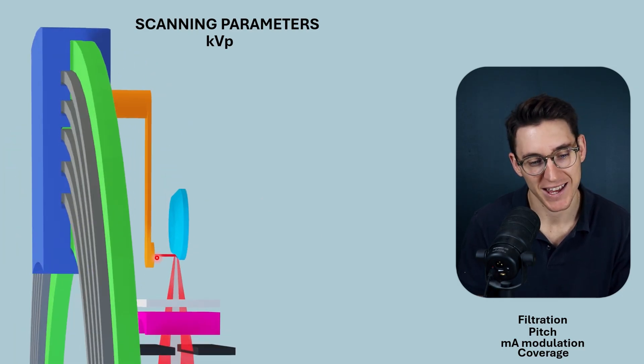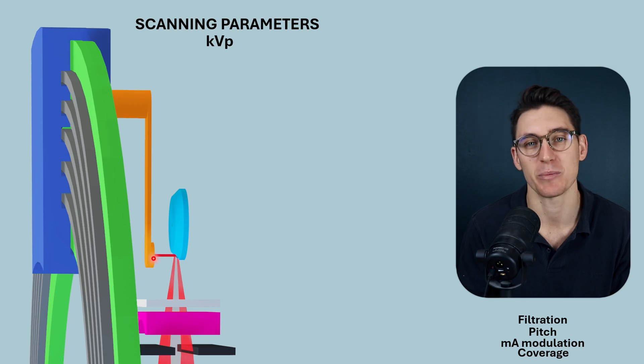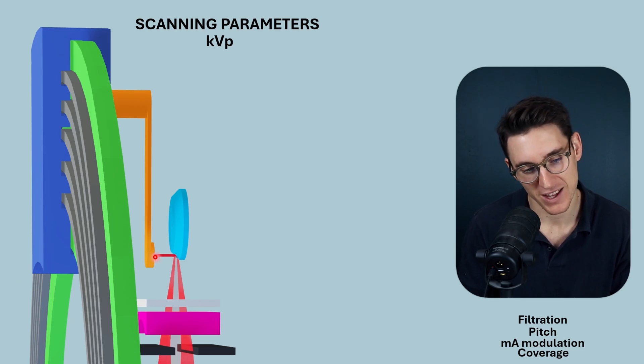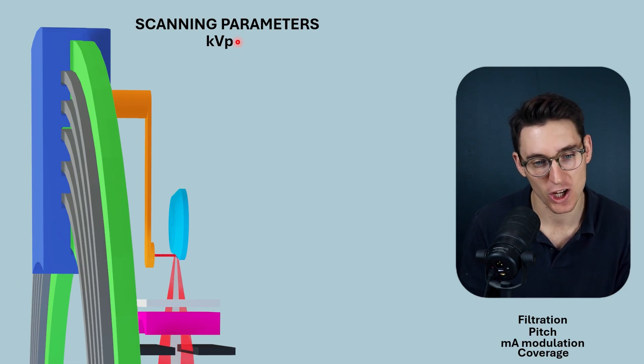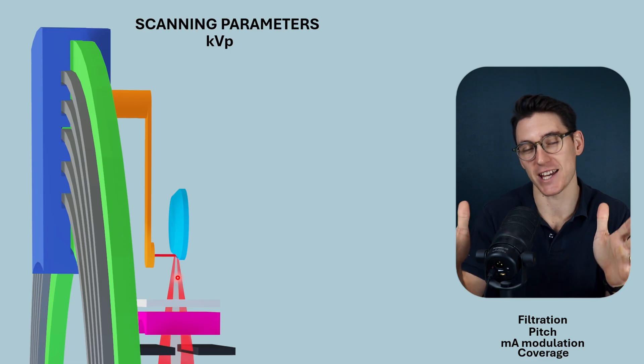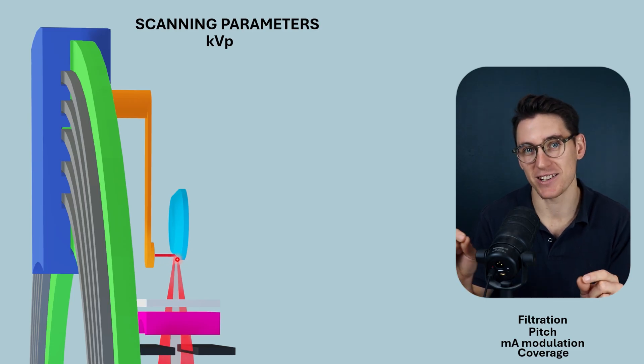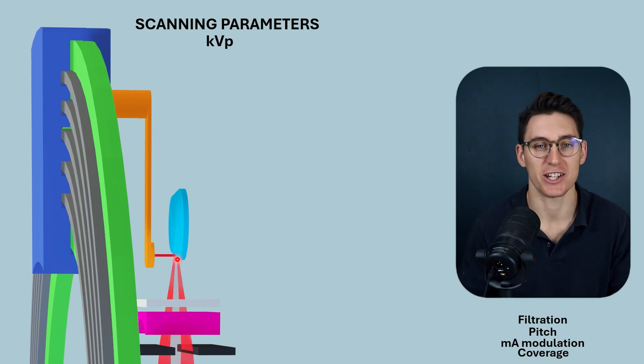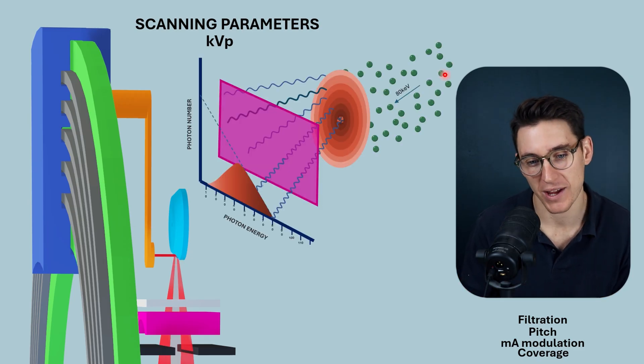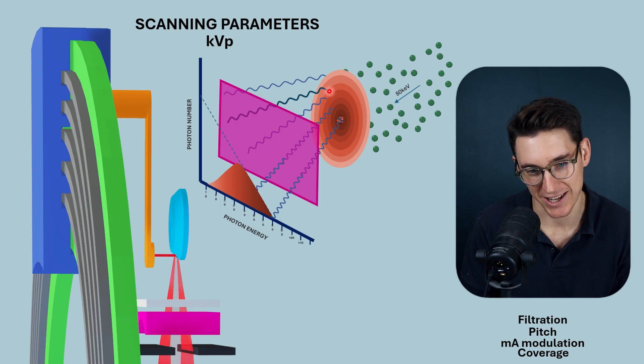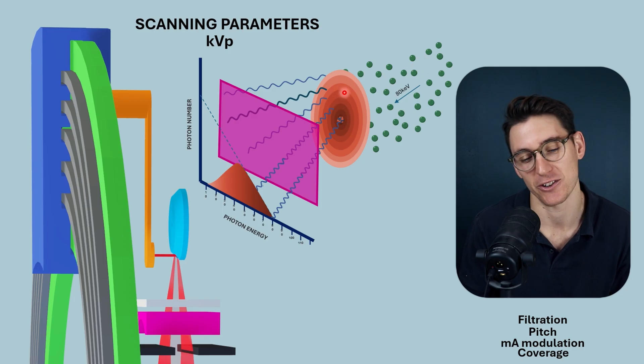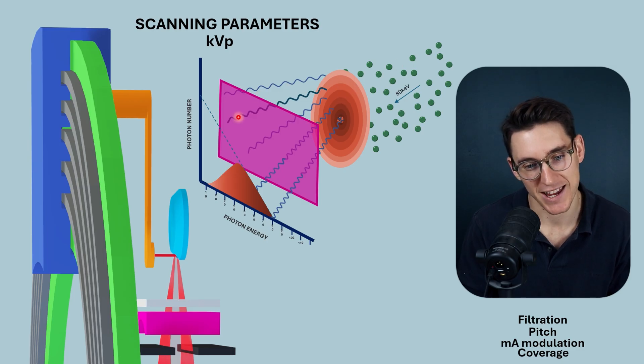Specifically, we produce x-rays by accelerating electrons from the tungsten filament in the cathode towards the anode. The number of electrons and the energy at which they are accelerated between the cathode and anode is determined by the KVP. Those electrons strike the anode and create x-rays in a spectrum consisting of Bremsstrahlung and characteristic x-rays, containing different numbers of x-ray photons at all the different energy levels.